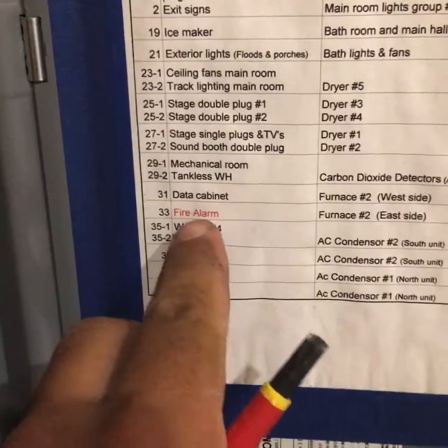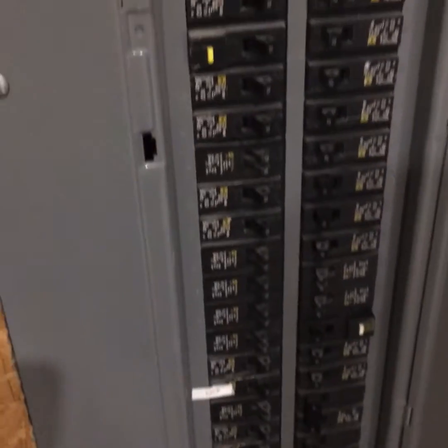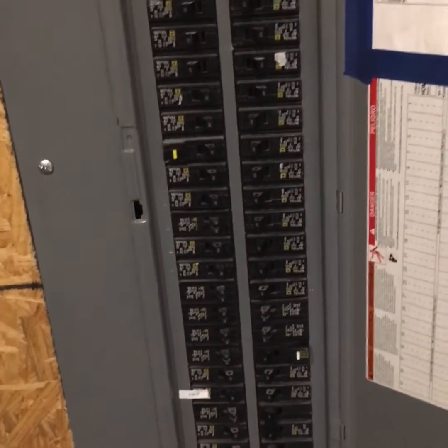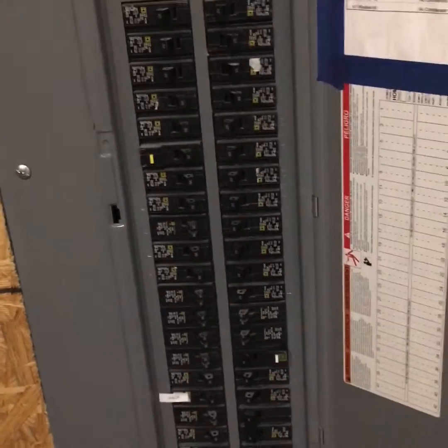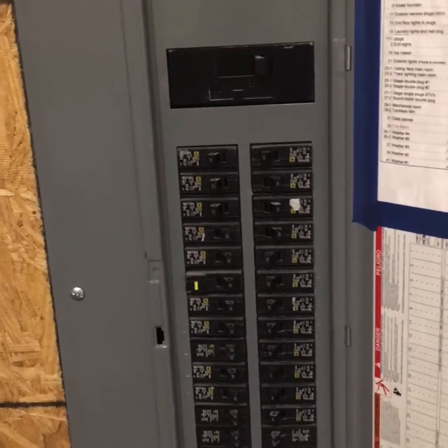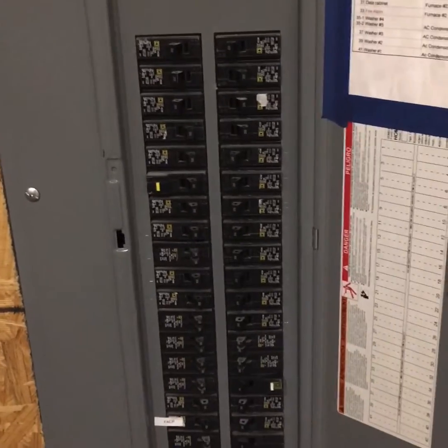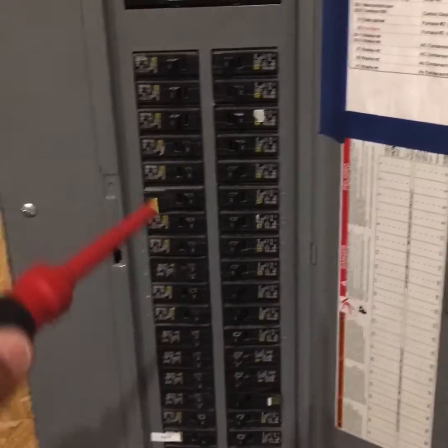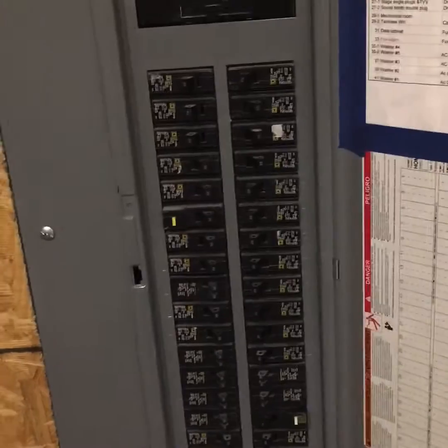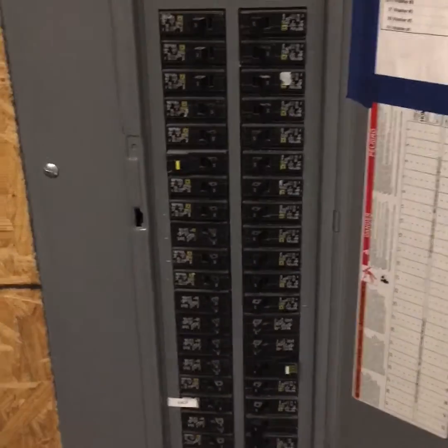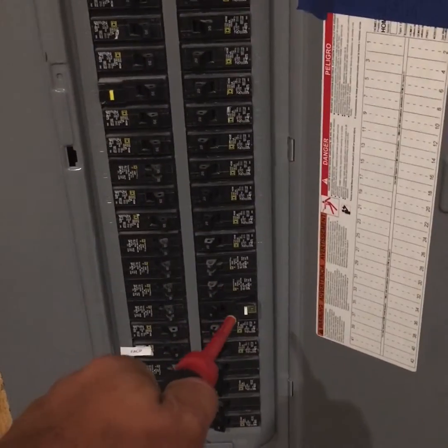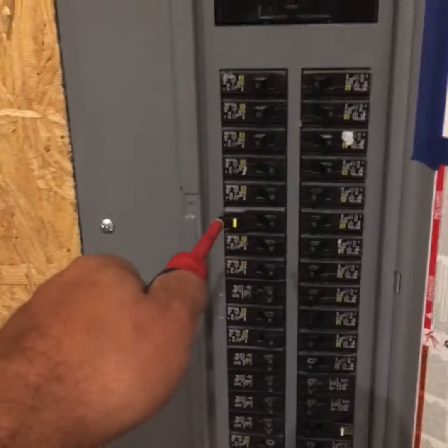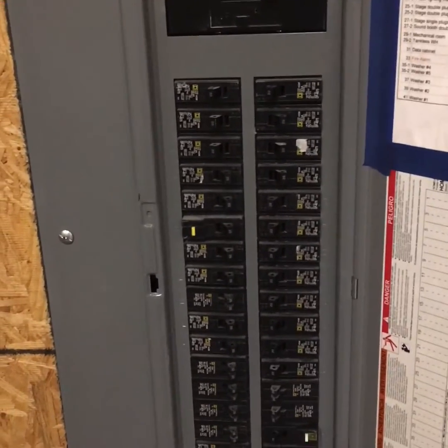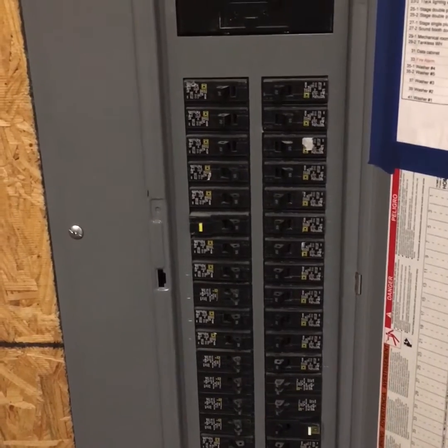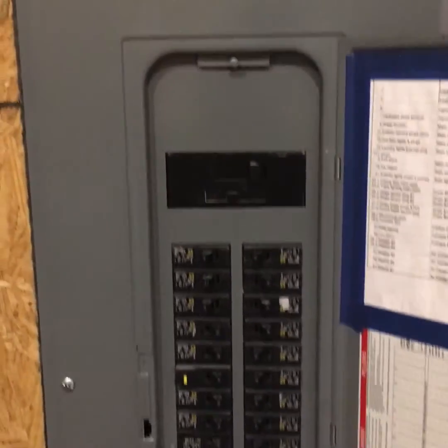But one other thing too, you want to make sure, like, this is my fire alarm. It's identified as red. And then I also have a sticker here. And then also, this is obviously not code compliant to 2020 or even 2014. There are no codes in Southeast Missouri. There's not even a state regulatory board in Missouri. So I put this in. There are no bedrooms or dwellings. I honestly don't know what the arc fault requirements are for a commercial building. This is more of a commercial building. I have an arc fault here for my CO2 detector, and I have a GFI for my exterior plugs, and that is it. I have GFI receptacles in the bathrooms and so forth to meet that code issue there.